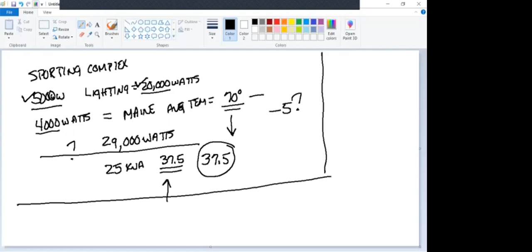That's going to be my answer. So you got, not only do you have to factor your total wattage to get to your transformer, you also got to factor where you're at. The rest of the questions are going to be similar. What's going on here is you're computing not only what the wattage is and what you need to do, you're computing where you're at. You got to use a little bit of brain cell matter to get out there. Well, I'd rather be safe than sorry and go to a 37.5 kVA than have to come change that back out. Now the question's not finished. What size fuse do I put in that transformer?